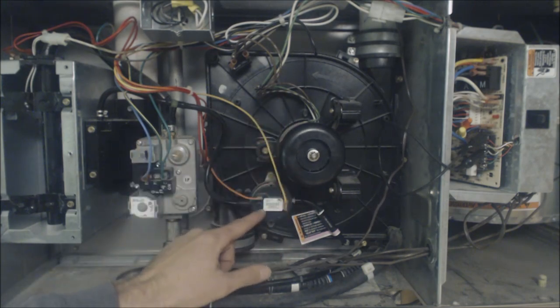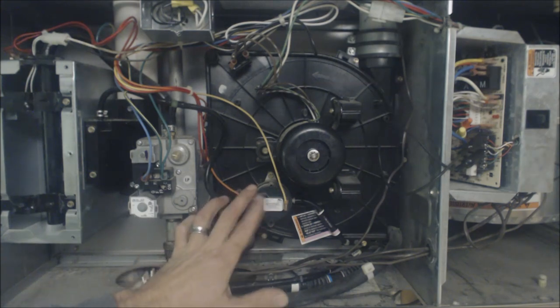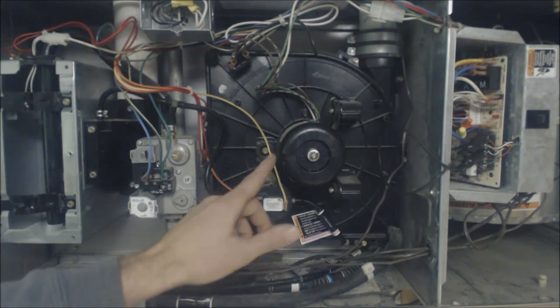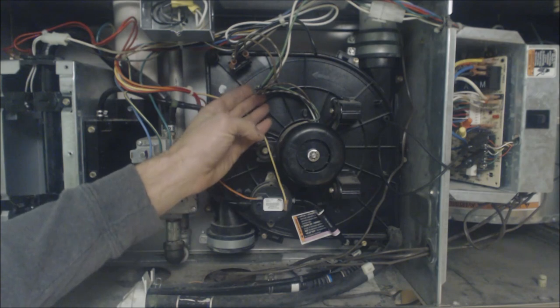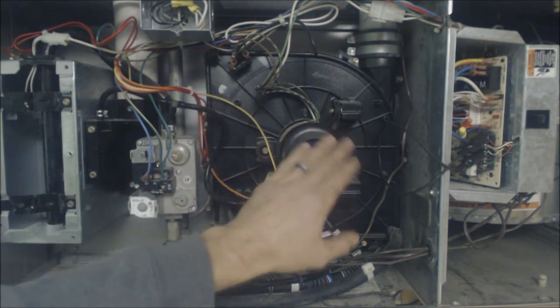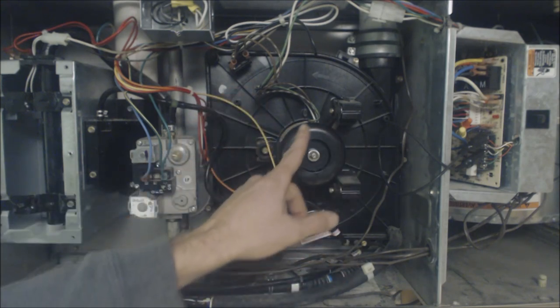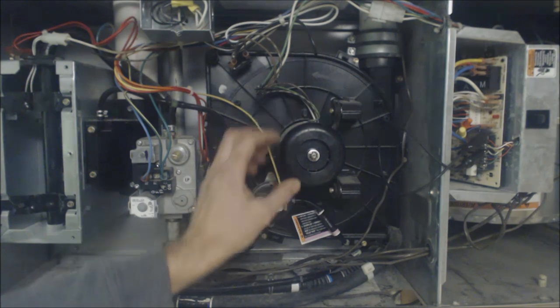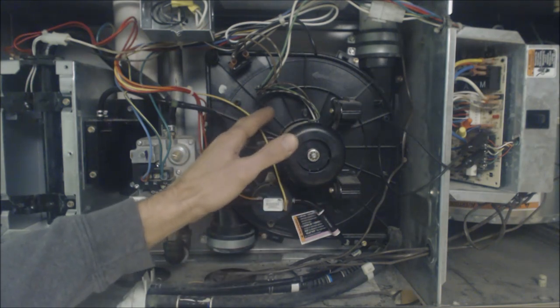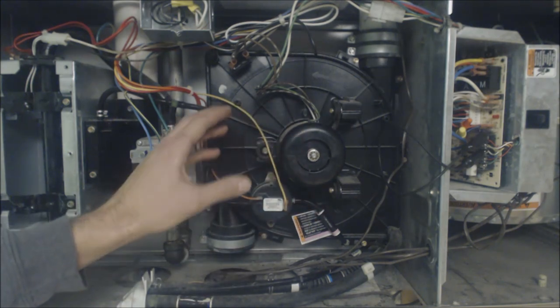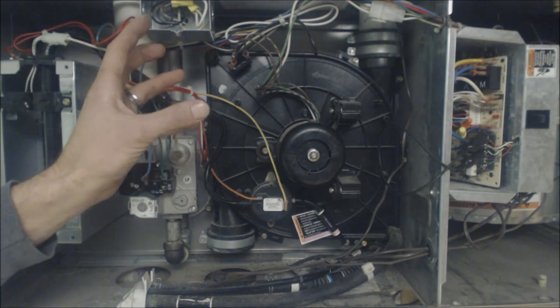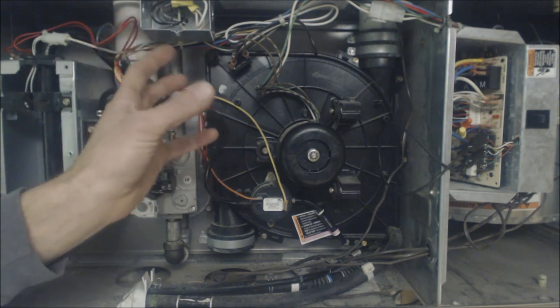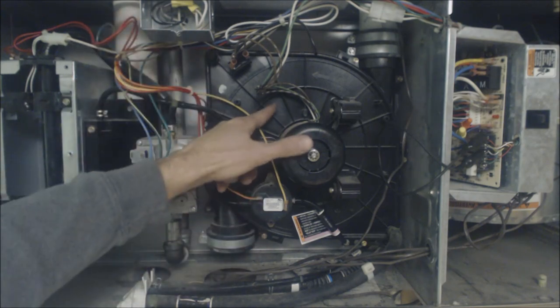The inducer motor may not even be turning on, maybe that's why this is not registering negative pressure. Another thing is you might hear rattling around in here while this is running. I'm not talking about the squeak when this thing turns off, I'm talking about a constant rattling inside that could be the blower motor wheel breaking apart.